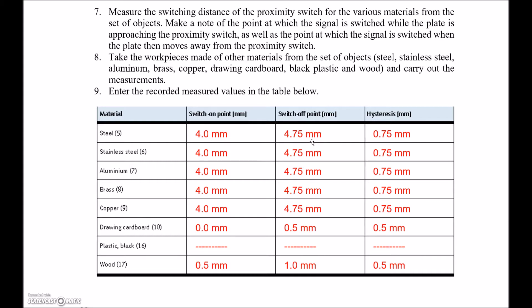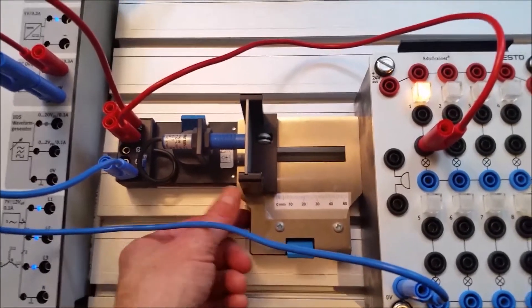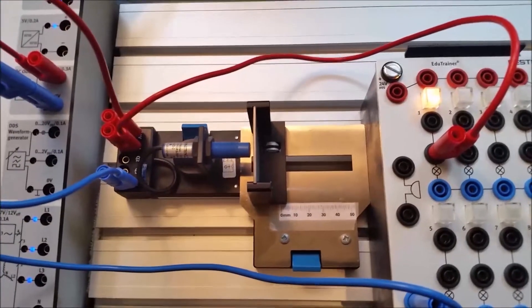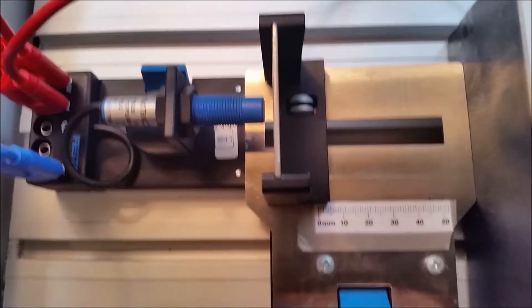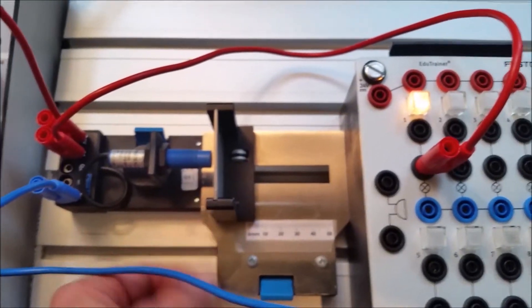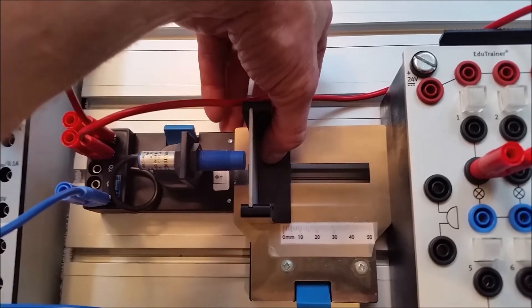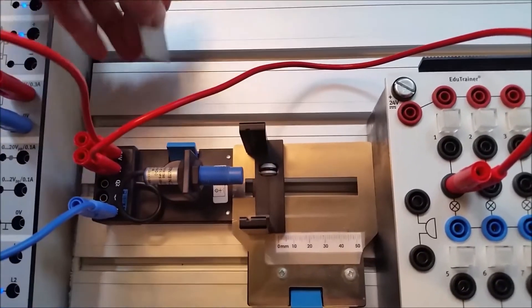Starting with number five, the galvanized steel: I'll back it off until it turns off, then slowly bring it forward with the thumb wheel. At that point it's turning on. Zooming in, it looks like the capacitive sensor is seeing the steel at about four millimeters away. The back of the slider reads four millimeters, and that corresponds to the distance right at the sensor face. Backing it off half a mil to a mil, it turns on at four and turns off at about four and a half or five.